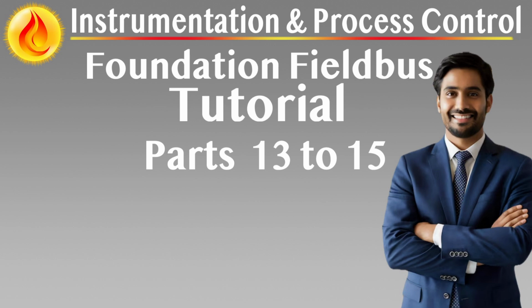The device description, DD, is a standardized text-based file that defines how a host system should interpret the data structures within a Fieldbus device. It describes the layout and behavior of function blocks, transducer blocks, parameters, operational modes, alarms, and supported commands. DDs also include information on units of measurement, default values, data ranges, access rights (read-write), and display formatting, allowing hosts to present a consistent, user-friendly interface regardless of device manufacturer.